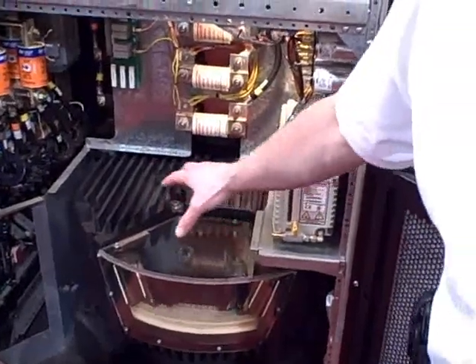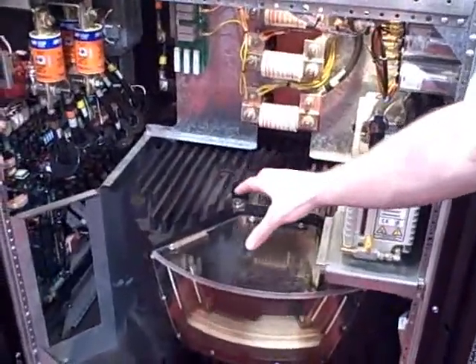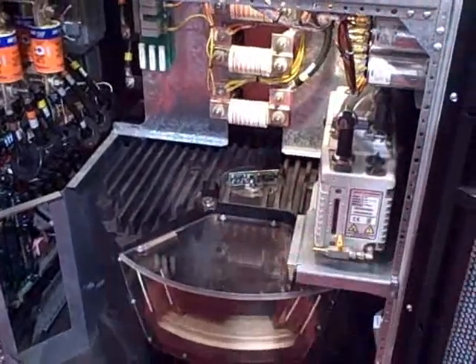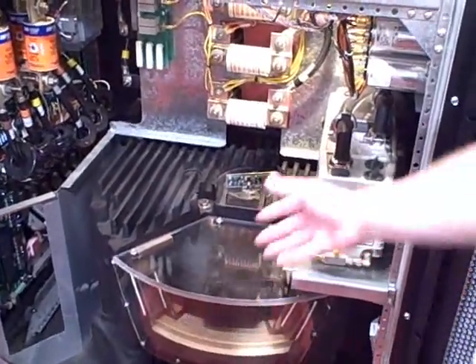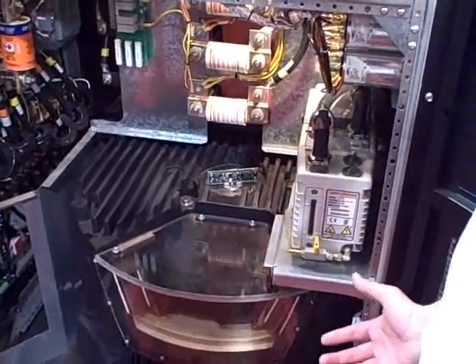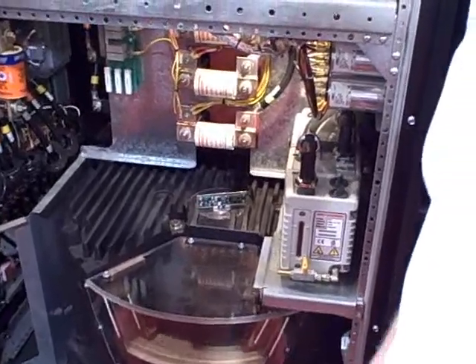It's not spinning at its real speed — this is just a demo system. We spin at about 7,700 RPMs, and it stores a certain amount of kinetic energy. In any event of a power outage, we discharge energy from the 250 kW wheel, and that gives you approximately 15 seconds of ride-through. That 15 seconds is enough time from when you have a power outage until standby generators pick up the load — bridging from one power source to another, from main utility to a generator.